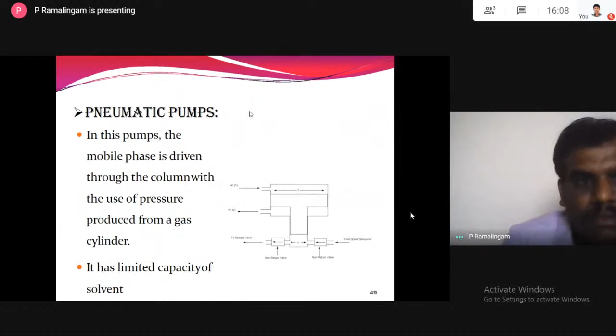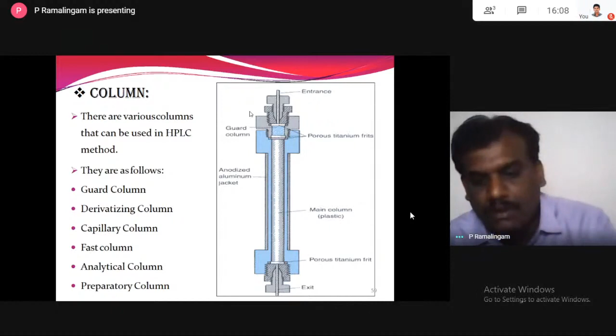So now let us come to the column, the HPLC column. There are various columns that can be used in HPLC. They are the guard column, derivatizing column, capillary column, fast column, analytical column, and preparative columns. The guard column is a small column placed before the analytical column. It is a kind of protection, used to prevent damage to the main column or analytical column.